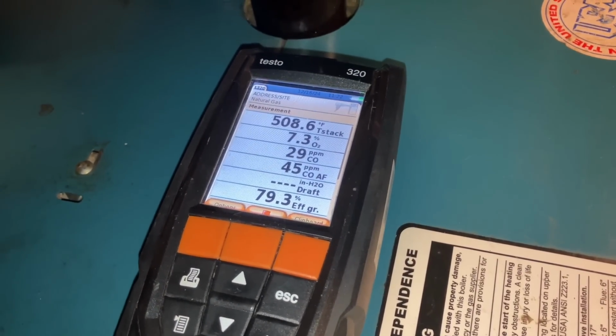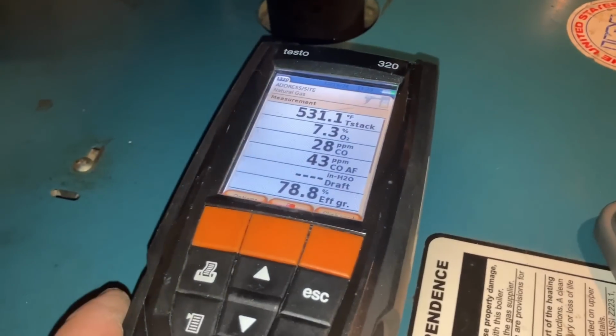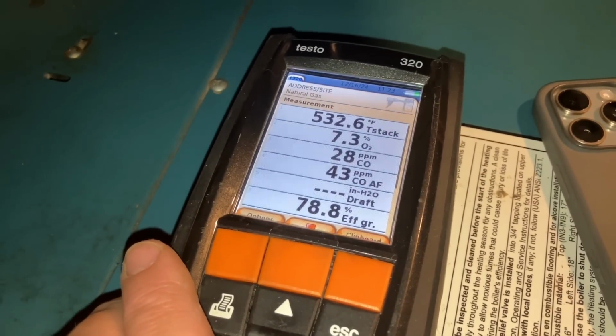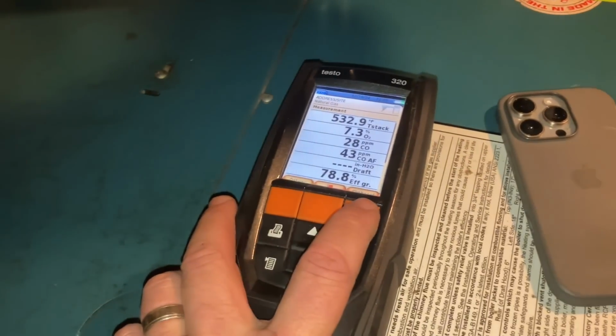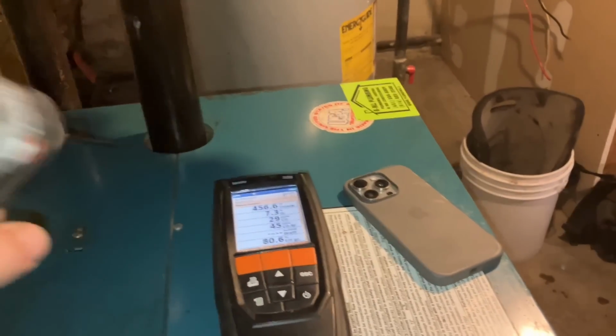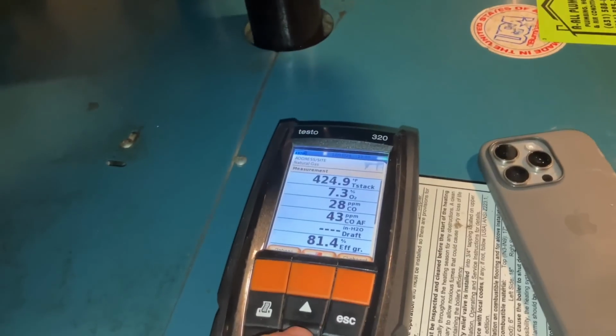The boiler is also 23 years old, keep that in mind. All right, so it looks like we're hovering around 530 degrees here. It's going up and down a little bit. We're gonna clipboard these numbers. Take our probe out, put it off to the side, and we're now going to do draft tests.